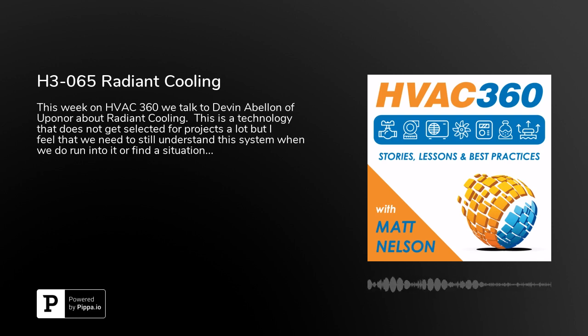But some of the common problems we see are, first off, not really being able to quantify or understand what the operating conditions need to be in order to satisfy a certain load. We talk about what you can expect from a radiant cooling system, let's say a floor application with bare concrete. You may be looking at 12 to 14 BTU per square foot, and that's really driven by the minimum surface temperature that ASHRAE recommends.